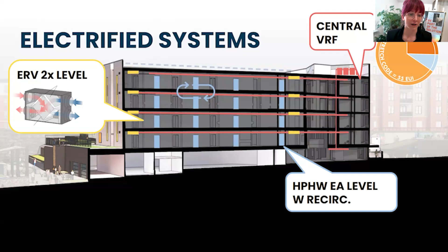They vent out the facade. And then on the roof, there's a centralized VRF system going into each of the units. All of the units have their own controls. You have heating and cooling simultaneously. And this again was a decision by the owner. They pay for the utilities. Part of the value to POA as a long-term building owner is that they are directly seeing the benefit of the performance of these projects. And so by having the central system, they can right size that equipment, where it's very hard again to find equipment that's a small enough BTU per unit when we're passive house, because we're using such small amounts of energy.